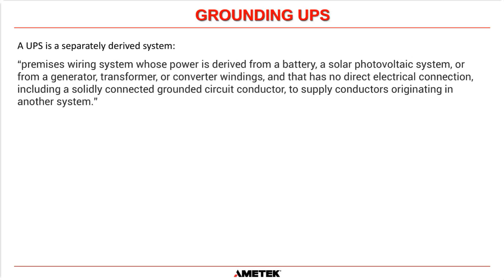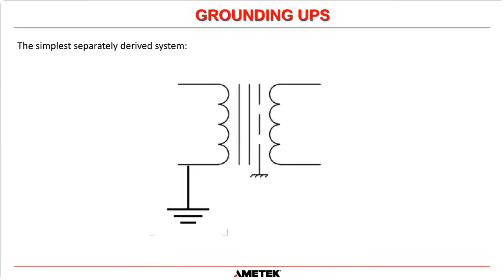The easy way to look at it is it's a separate system where the ground connection can be completely separate to the original grounding in the building. Hopefully, as we go through these slides, it will become more apparent. So the simplest separately derived system is an isolation transformer, a transformer where the primary winding and the secondary winding have no electrical connection to each other. None of the wires physically touch each other, okay?